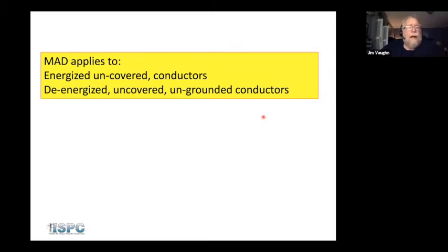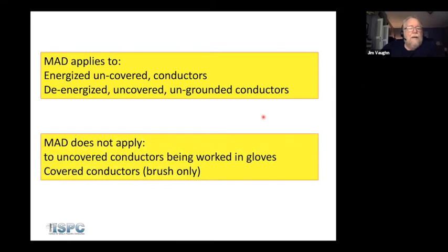If you are working in absolute isolation and you've got control of the switches and your tailboard says that you're working in isolation and everybody understands that, then you can work without gloves, you can work without grounds. There are risks associated with that. You simply have to understand what those risks are. But if you're just working de-energized, not in an isolated work environment, then you are required to cover it or work it as if it's hot. MAD does not apply to uncovered conductors being worked in gloves, and that's the ones that you saw in that man in the picture.